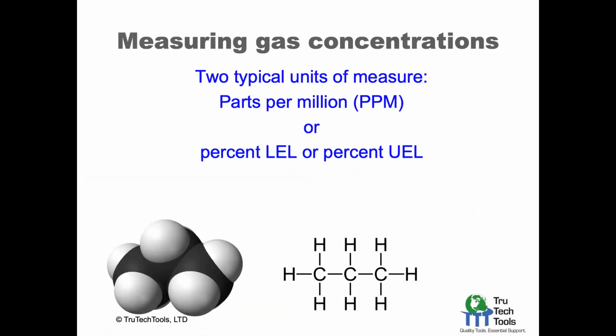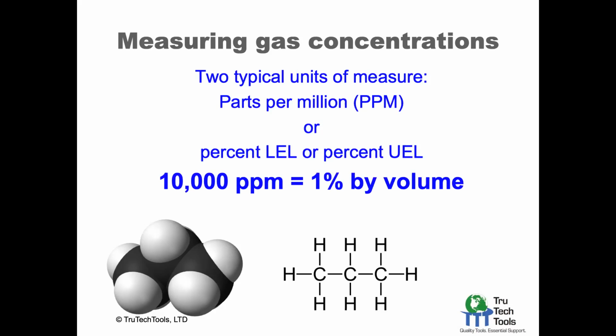So the typical measure for concentration of gas for combustible gas is parts per million, again, sort of like CO, or exactly like CO, or percent LEL or percent UEL. So as it goes through different phases, the ppm measurement is a lot lower concentration. The percent LEL gets to be higher concentration, and we'll show you how that kind of scale works. And again, this just goes back to basic, actually it's math. 10,000 ppm equals 1% by volume.